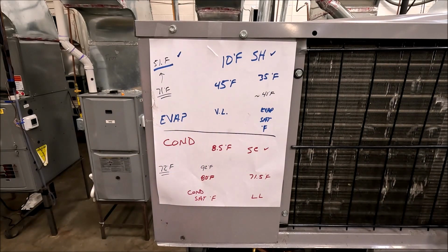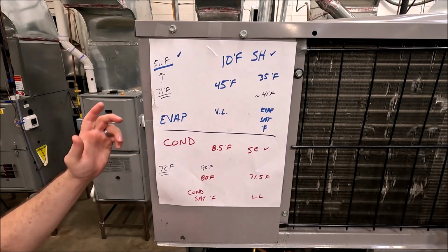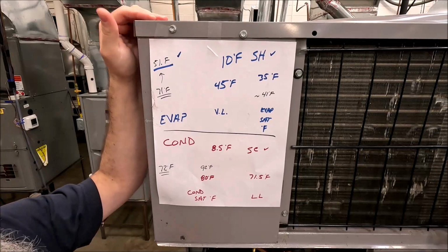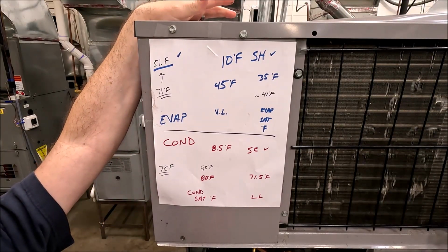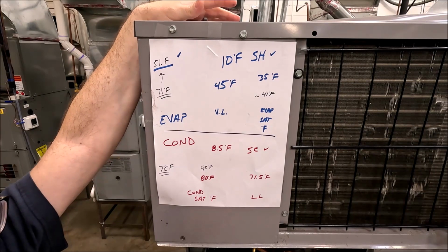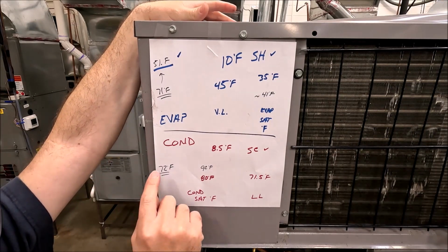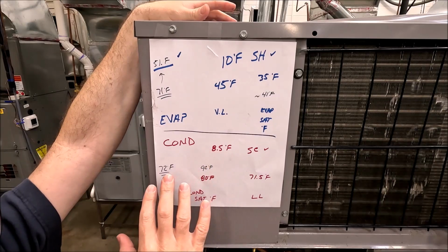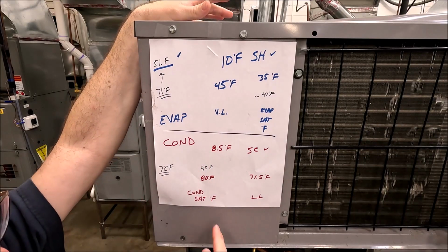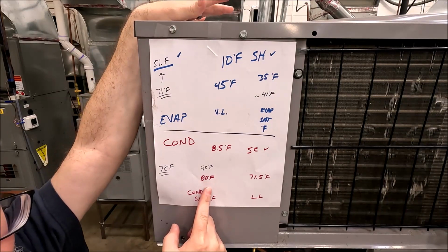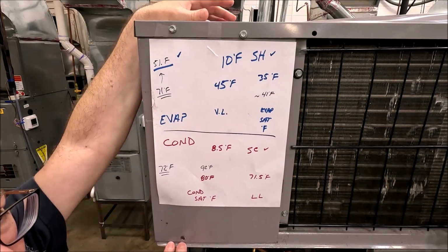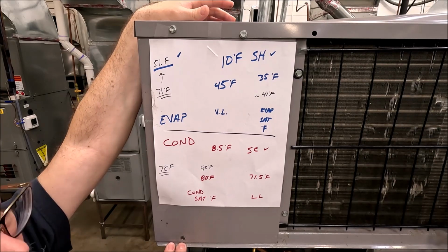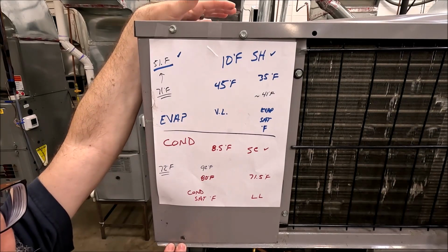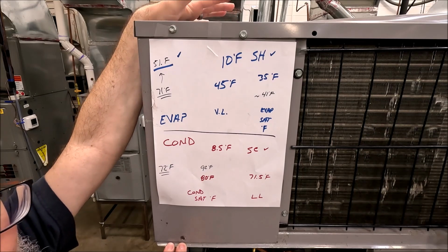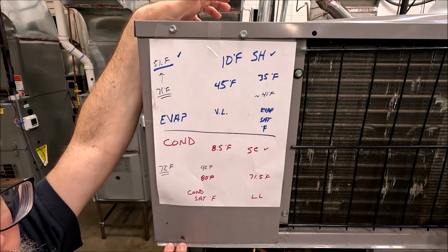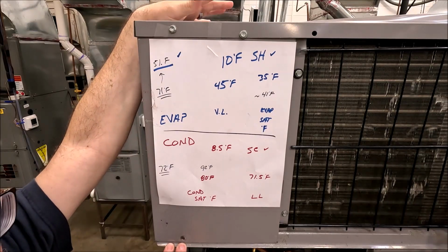This is one of those where, probably in my case, because I'm inside and it's so cool and the humidity's down and stuff like that, you're going to come across a spot where you're using a troubleshooting chart and you've done your basic checks and it looks good, it feels good, but then you get this weird thing like my saturation temperature is off. That's going to be where experience comes in and teaches you. Sometimes there's not a perfect answer. You have to make your best estimated, educated, you know, do right by the customer. You have to make that call. I wish there was a better way for me to explain it.